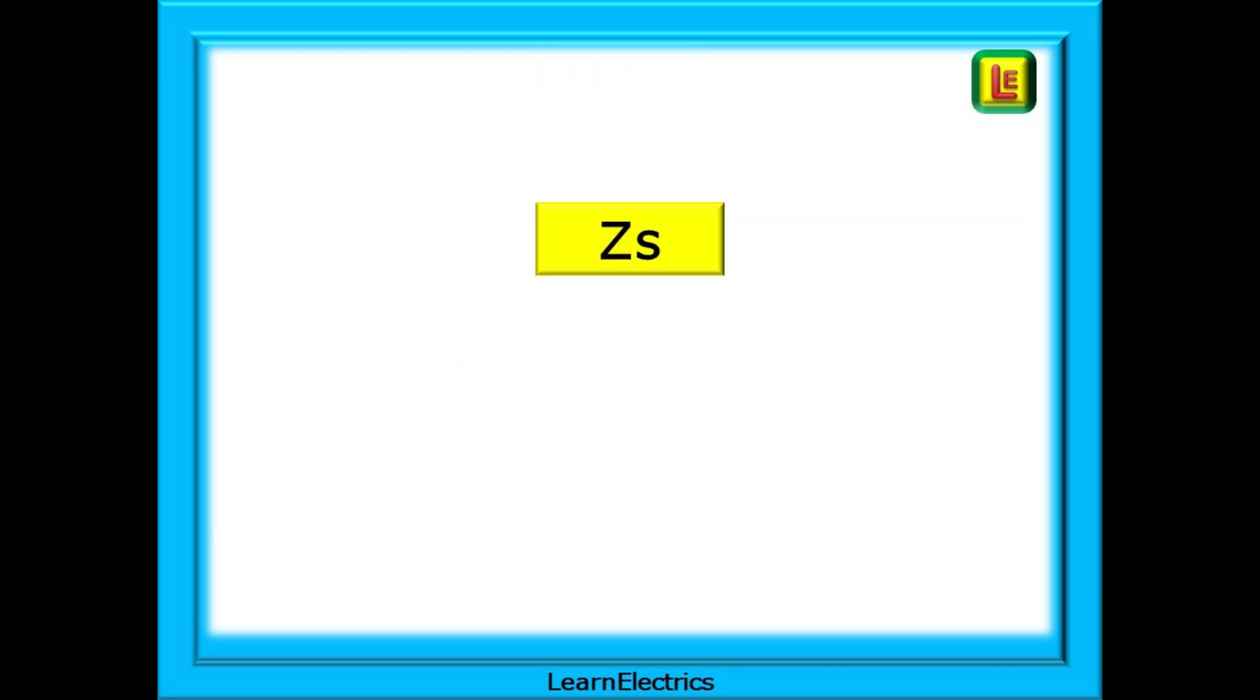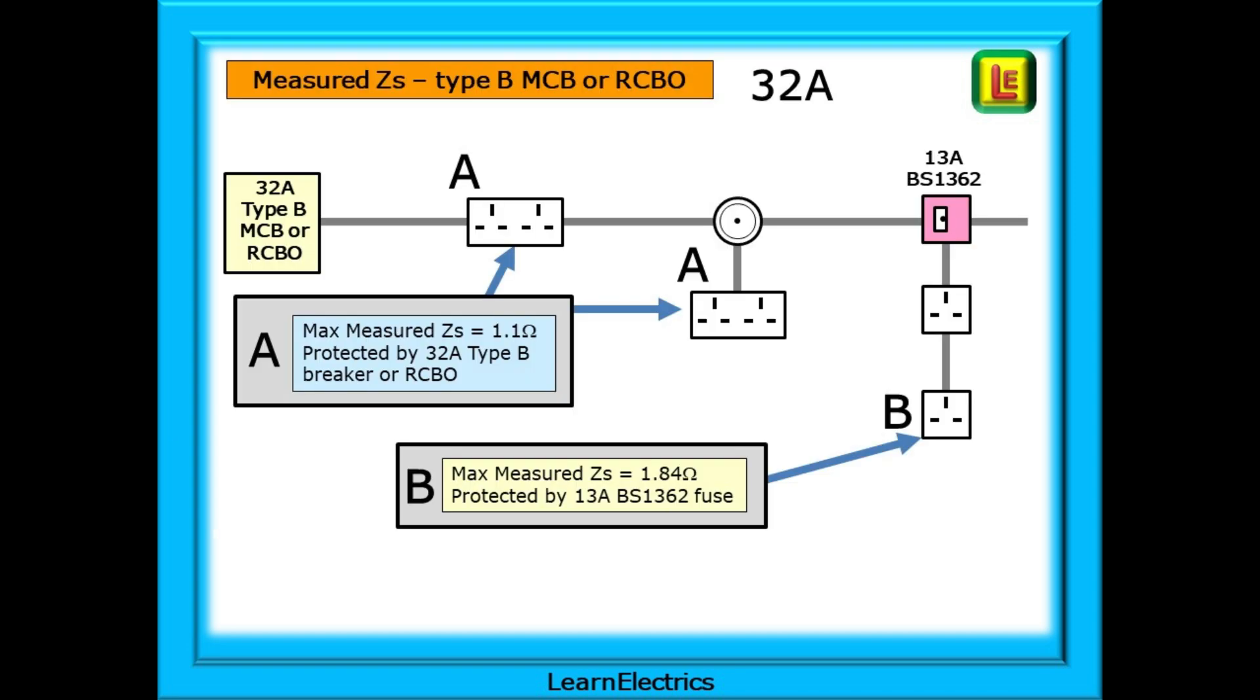The next question is about ZS. Does this change if we add spurs to a circuit? Let's take a look. At point A on this drawing, the socket outlet on the ring and the socket outlet spurred off the ring are both protected by the 32 amp breaker at the consumer unit. If this was a type B breaker or RCBO, we would have a maximum ZS of 1.1 ohms for both of these outlets at point A.